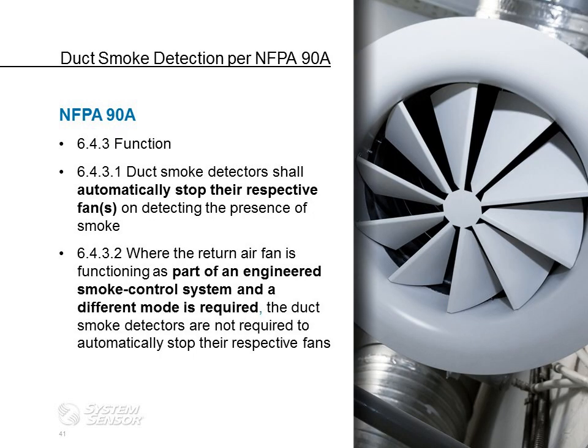The industry in general, the rule of thumb, is that if a unit is larger than 2,000 CFM, you're going to be required to install at least one duct smoke detector, whether it's International Mechanical Code or NFPA. The true difference is where you locate it.